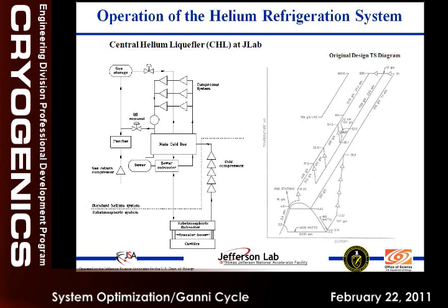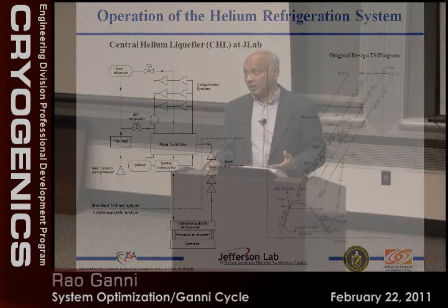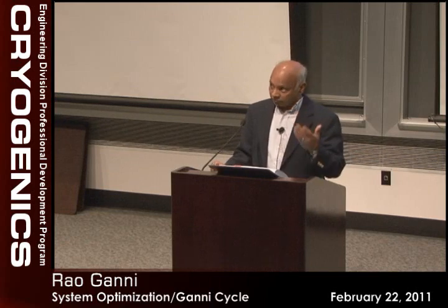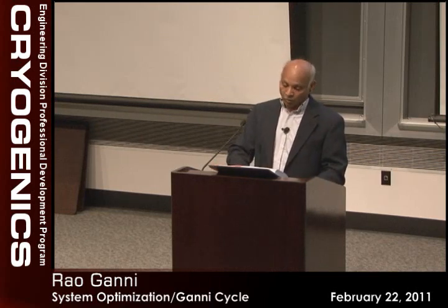Same thing, we started with reciprocating compressors. Every 6 months to less than a year, we used to have a valve leakage problem, oil carryover problem. So we slowly introduced the screw compressors around the late 70s, early 80s. And once we understood the oil carryover problem, now our compressors are running 70,000, 80,000 hours around the clock, whereas the screw compressor manufacturer will tell you around 35 to 40,000 hours, and you have to rip it apart and maintain it, change all the bearings, thrust bearings and everything. And we don't do that. We figured out how to extend the life even beyond what the manufacturers thought. So we came a long way in producing highly reliable components along the way by working with them and understanding their behavior more and more.